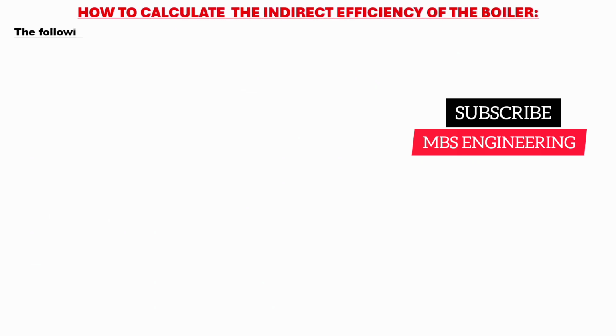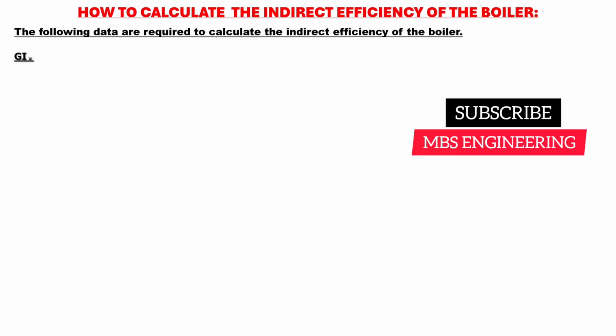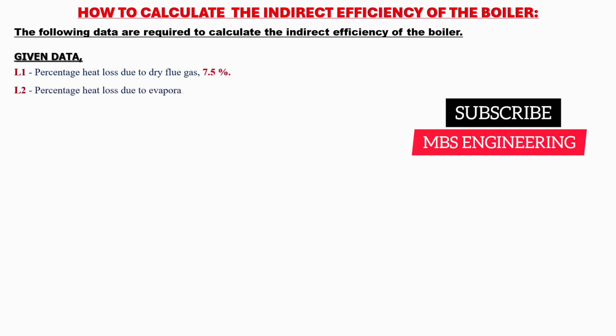Next, we will learn and understand how to calculate the indirect efficiency of the boiler. The following data are required to calculate the indirect efficiency of the boiler. Given data. L1 is the percentage heat loss due to dry flue gas, 7.5%. L2 is the percentage heat loss due to evaporation of water formed due to H2 in fuel, 3.4%.